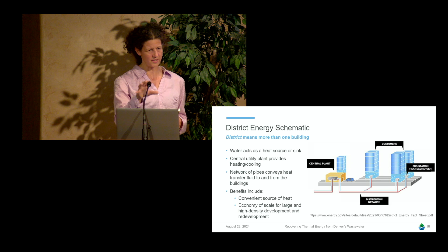For wastewater heat recovery and thermal energy from wastewater, the systems become expensive. We need to bring that water out of the sewer line, which involves pumping, and we need to clean it and screen it so we're not blinding the heat exchangers. That's really the majority of the cost — probably about 80% of the cost is right in that infrastructure. The actual heat exchangers, there's not as much to it in comparison.